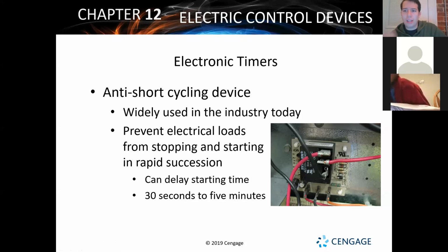So the last thing at the end of the last session we talked about was delay on make and delay on break timers, and how those operate and work. Now the other thing we've got is specifically an anti-short cycling device. I said that electronic timers can be used to prevent short cycling, which is basically the system coming on and off really, really quickly in succession.